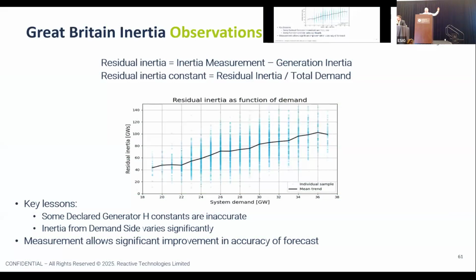Key lessons from the first deployment in the UK are that some of the declared H constants from generators will be inaccurate - and that's before you get to grid forming, Jim. Also, the inertia that you get from load varies significantly. If you start measuring it, you can really improve your forecasts and include that component within your planning and then into operations as well.